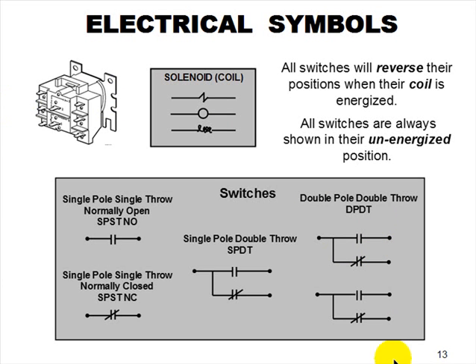And this is a typical double pole double throw plug-in relay we use all day long, fan centers, whatever. All right, the coil is across 2, usually the double terminals. All right, that's the coil. One side of the coil gets hooked up to a transformer. Other side of that goes to a thermostat. Other side of the thermostat down the other side of the coil. In series, you have the coil with a power source with a switch that's going to close it and send the power through the coil. When the coil is energized, all these switches associated with that coil are going to change position. That'll close, that'll open, that'll close, that'll open. Whether you use them or not, it's going to happen.